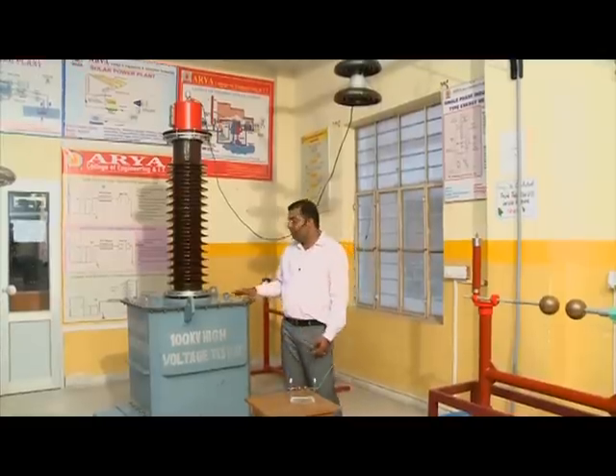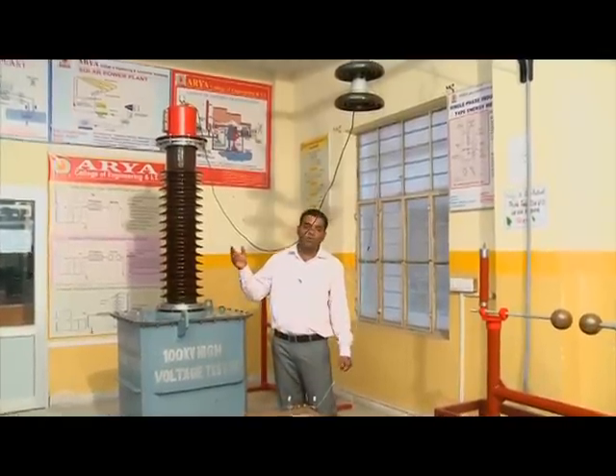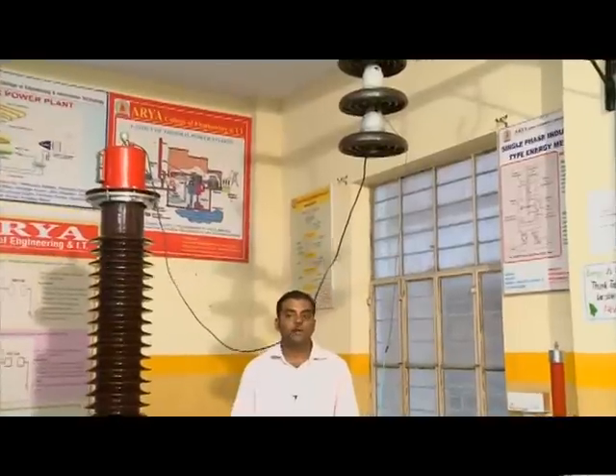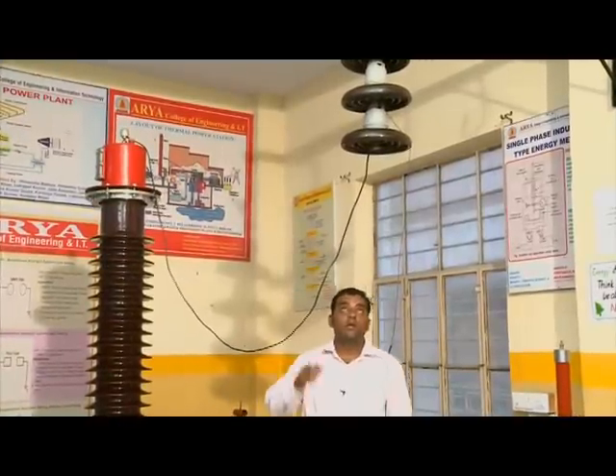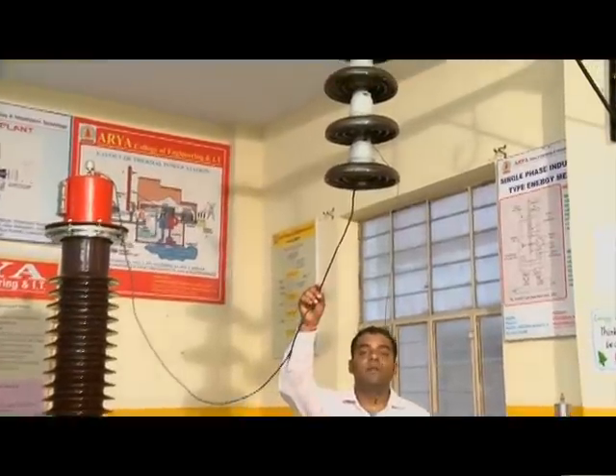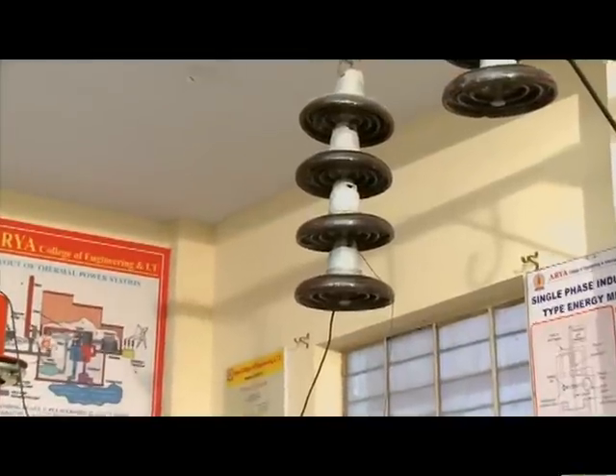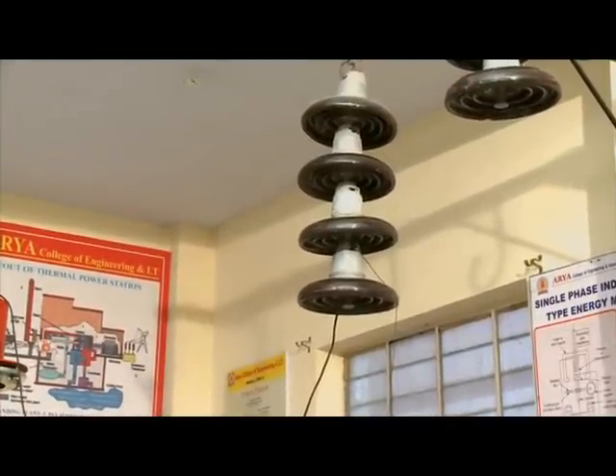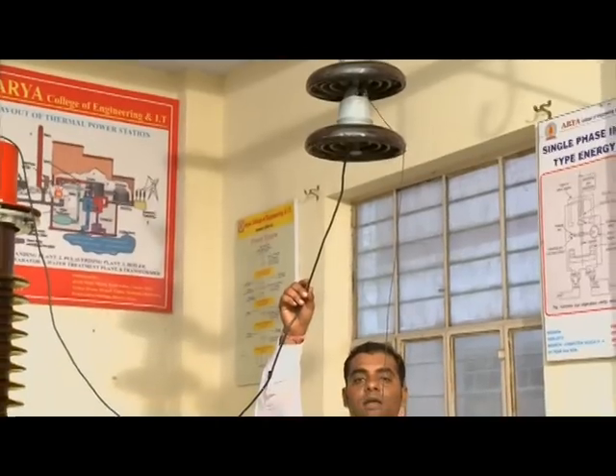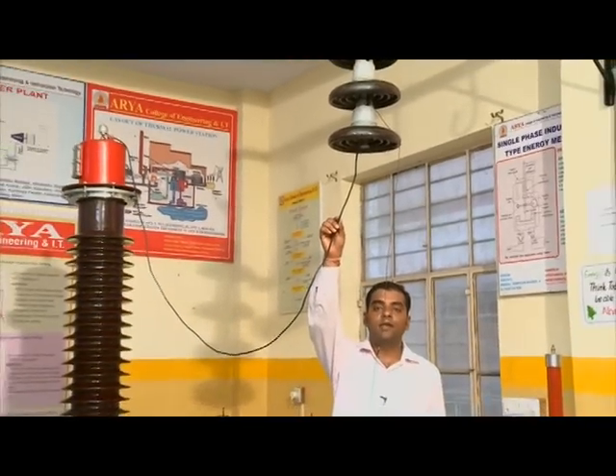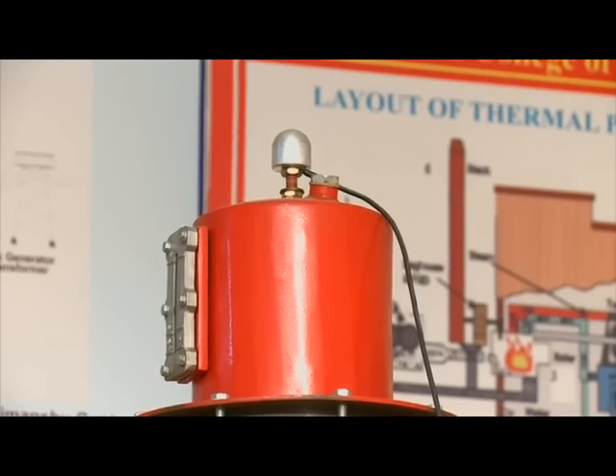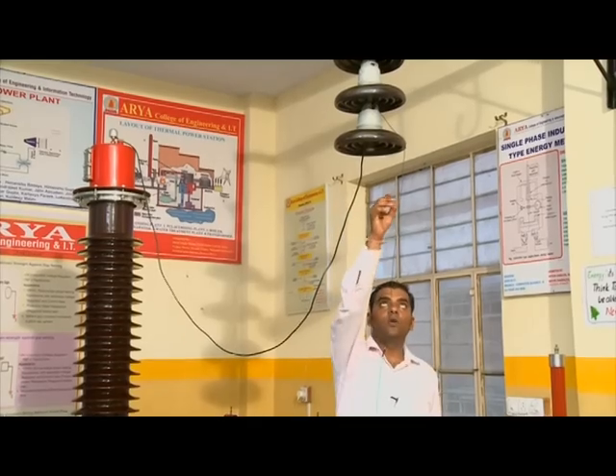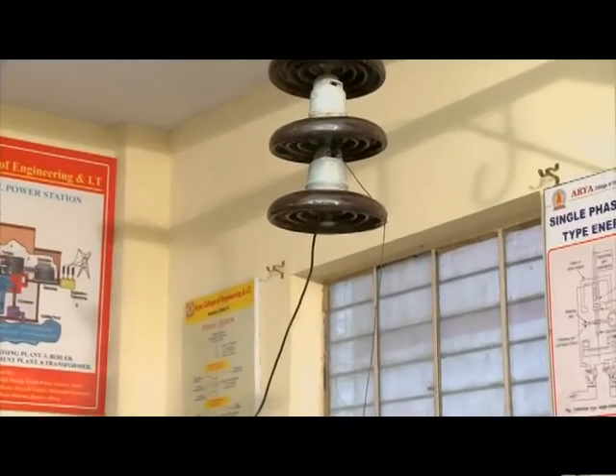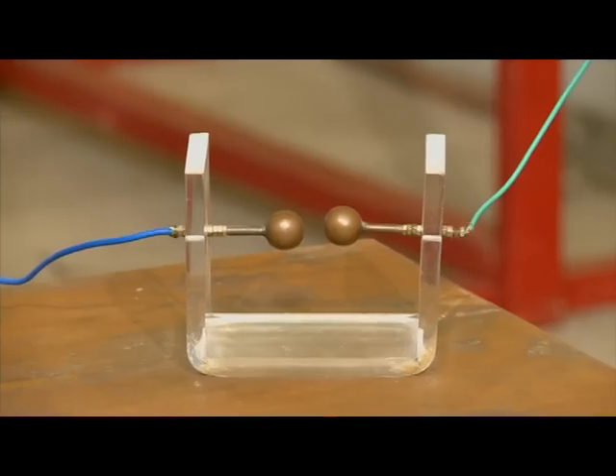In this setup, we have a transformer. The output voltage of the transformer is connected with the insulator string. In that particular insulator string, we have 4 units. Each unit is of 11 kV. First of all, we connect an individual unit of the insulator string with the output of the transformer, and the output of that particular unit is connected with the electrode.